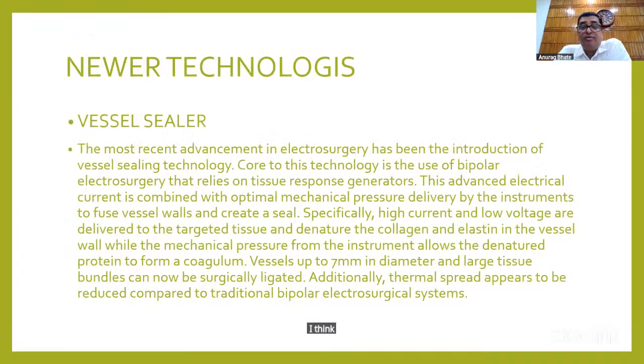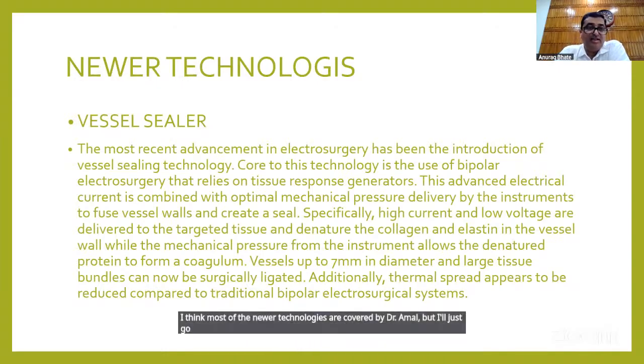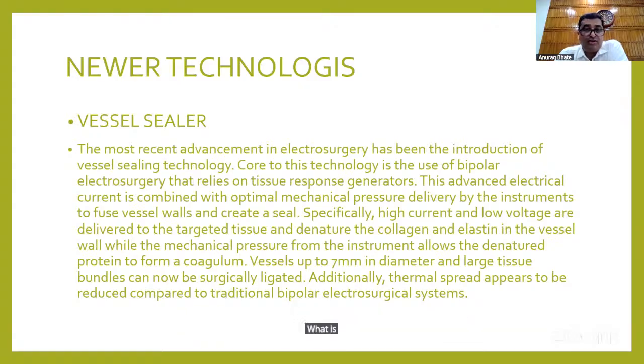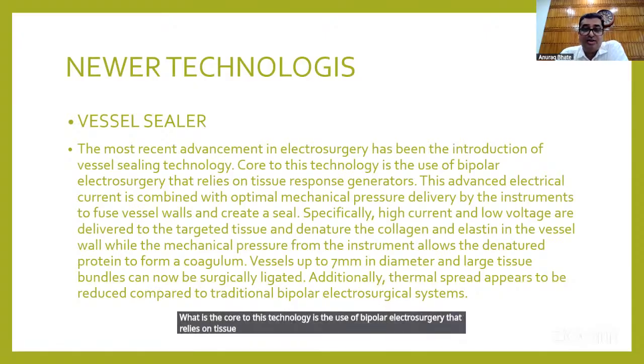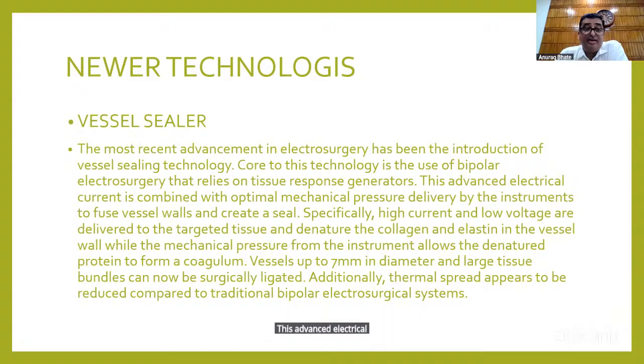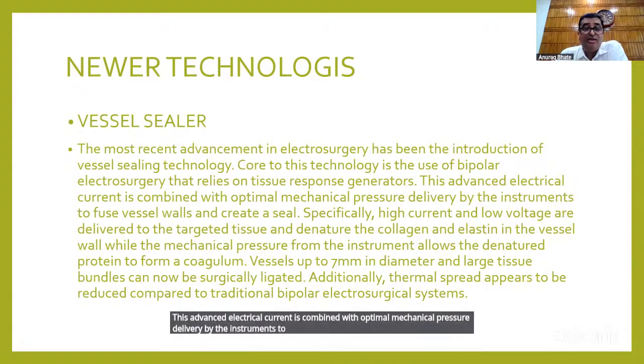I think most of the newer technologies have been covered by Dr. Amal, but I'll just go in short. A vessel sealer: the most recent advance in electrosurgery has been the introduction of vessel sealing. Core to this technology is the use of bipolar electrosurgery that relies on tissue response generation. This advanced electrical current is combined with optimal mechanical pressure delivery by the instruments to fuse vessel walls and create a seal.